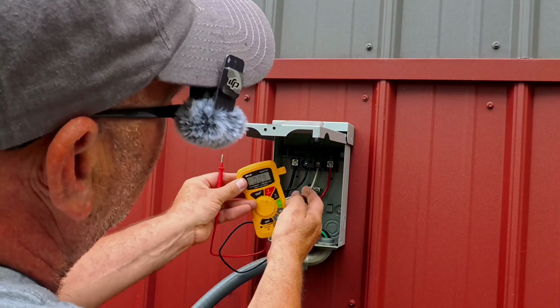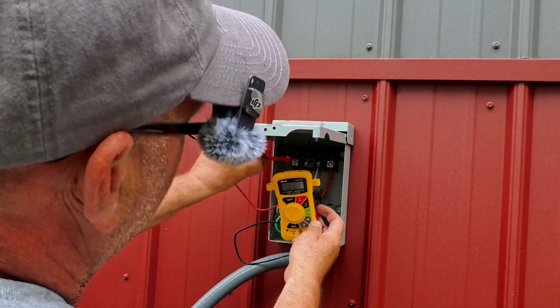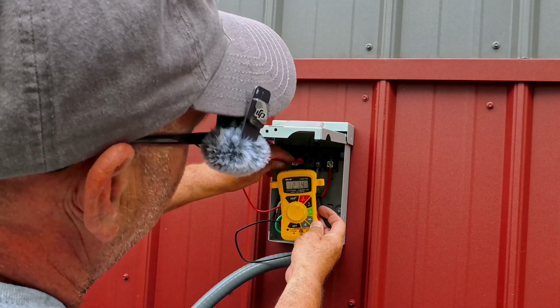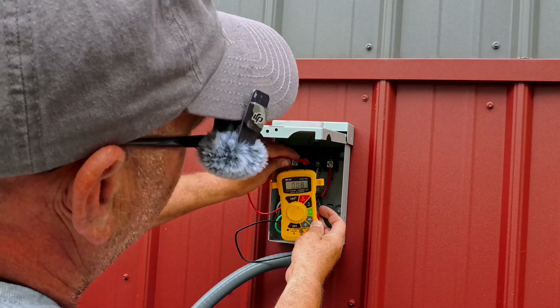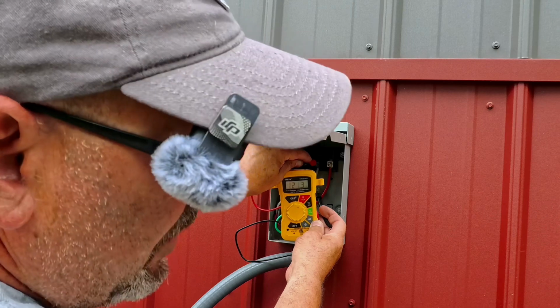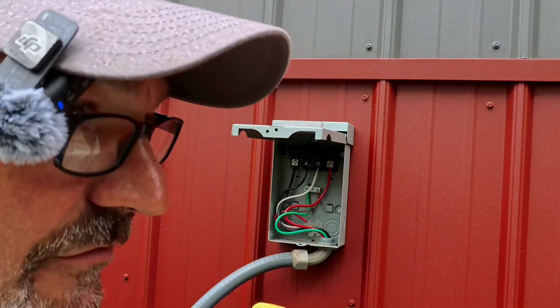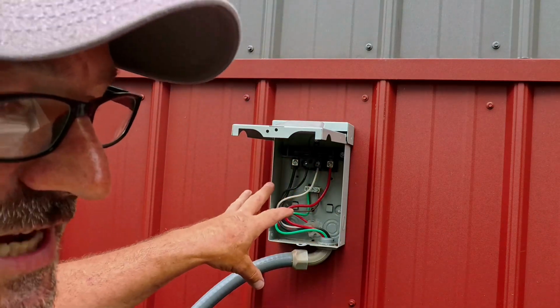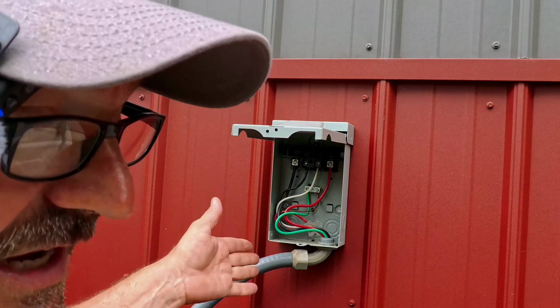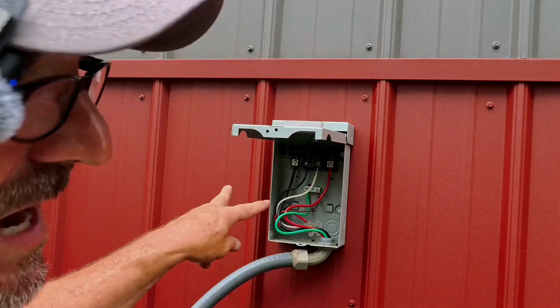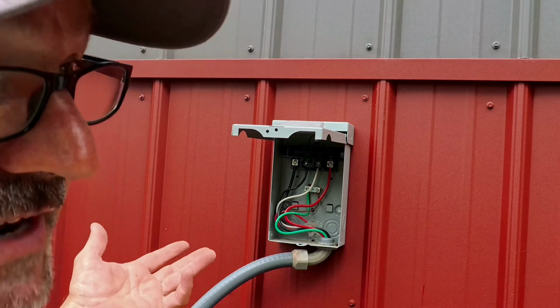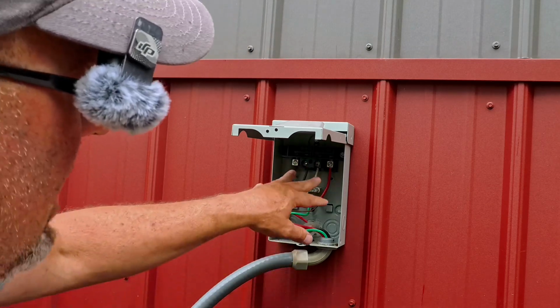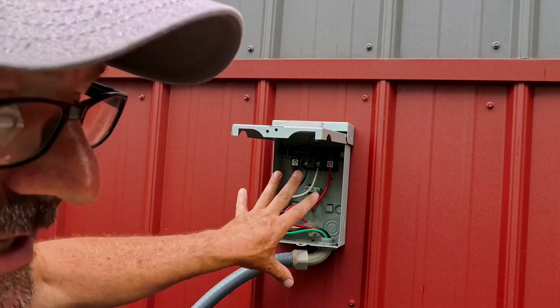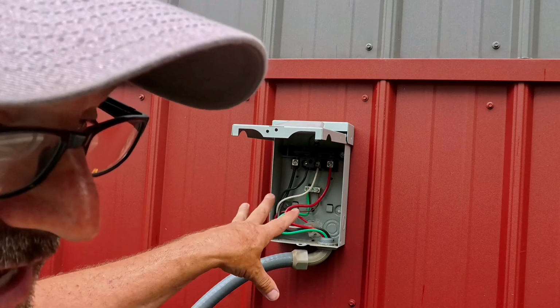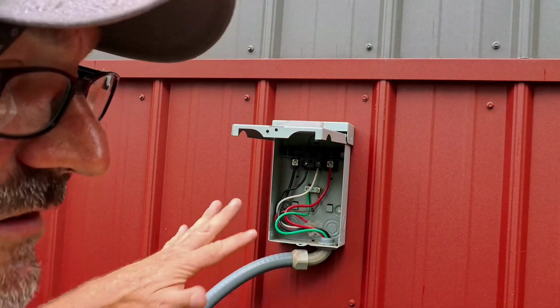So put in the black on ground, and then come up here and check our voltage to this line, 121 volts. Check this line, 121 volts. Combination of the 2, 240 volts. If we only had 110 on one line, on one leg, and not on the other, then we're going to go backwards into the breaker panel, because obviously we're having an issue there. So basically we got voltage coming here, so we're going to put this back together. We're going to put our service disconnect back in, and then we're going to go into the unit. Obviously everything's working good here.